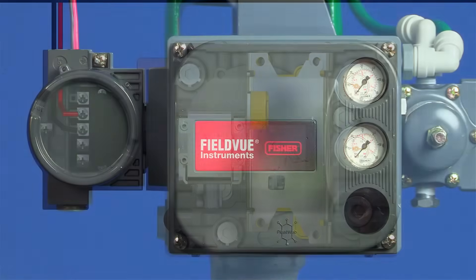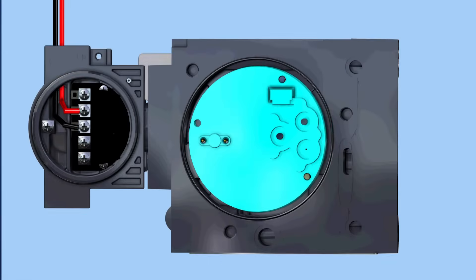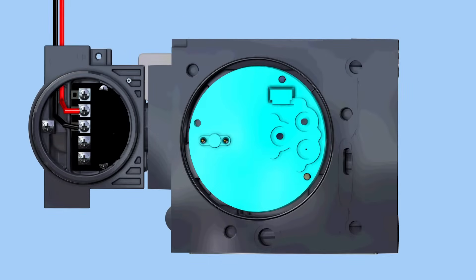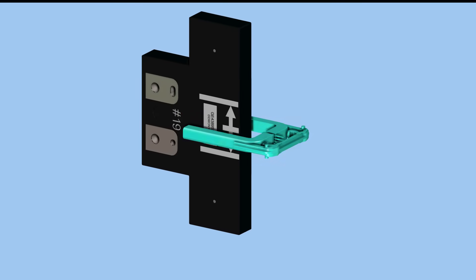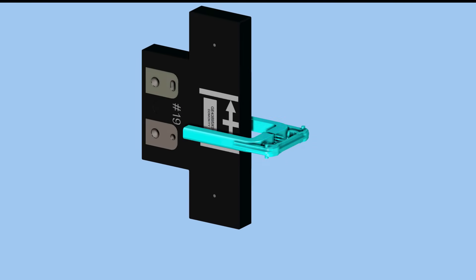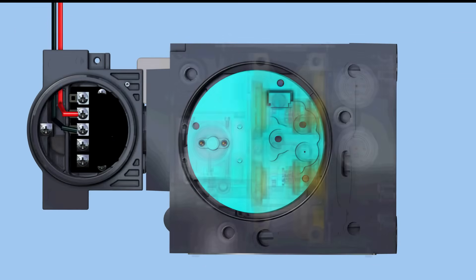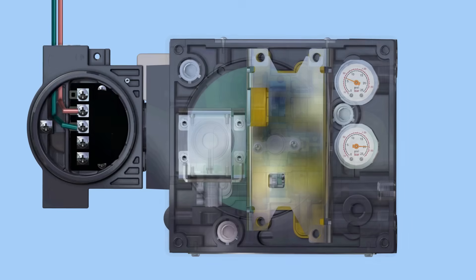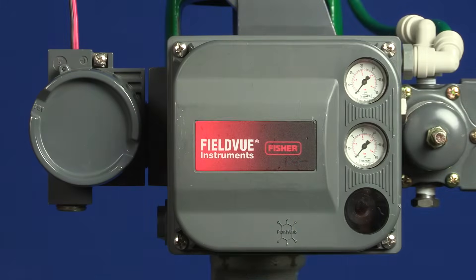In this example, we can see that the electronic control signal is sent directly to the microprocessor, providing an input or set point. Valve position feedback is sent to the microprocessor from an electronic sensor. The input and feedback are summed against each other to determine the error, and the microprocessor then calculates what output changes need to be made to correct that error.